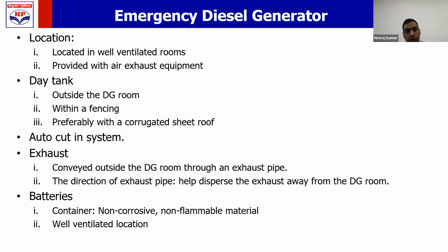The location of this exhaust shall be chosen so that it helps disperse the exhaust away from the DG room. So in that case, direction of the door and direction of the wind shall be considered, and then it should be decided where the exhaust of the DG should go.